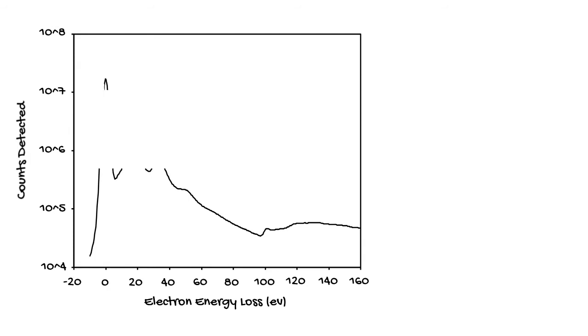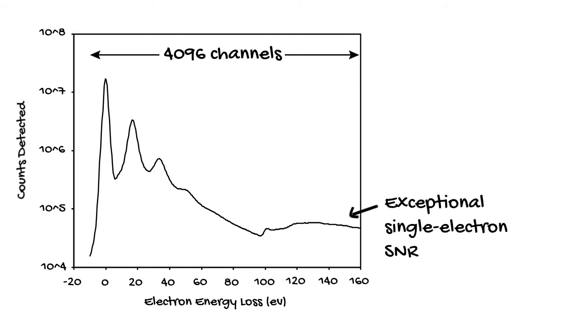So, are there any better options? Let's go back and rehash the requirements for a good EELS detector. The detector should have lots of channels, like 4K channels, so that your spectrum has sufficient resolution to detect features of interest. The detector should have exceptional sensitivity so that it can detect weak signals, especially in high-loss regions of the spectrum. And finally, the detector should have sufficient dynamic range to capture the entire spectrum for many different EELS experiments.